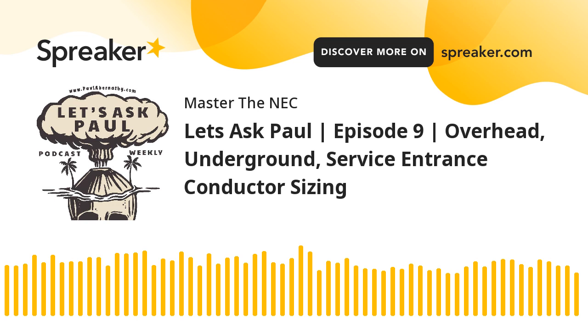All right, so for service entrance conductors, most people understand that when I say service entrance conductors, it also is going to cover SE cables, those type of scenarios where you have SER, SEU, and again, USE-2 could be utilized, USE could be utilized as service entrance conductors. So again, go back and follow Article 100 and you can see all the definitions and you won't have any problem. All right, so now when we're talking about service entrance conductors, we would look at 230.42, and this would be minimum sizing and ampacity. Now, in this case here, it says General (A), service entrance conductors shall have an ampacity of not less than the maximum load to be served.